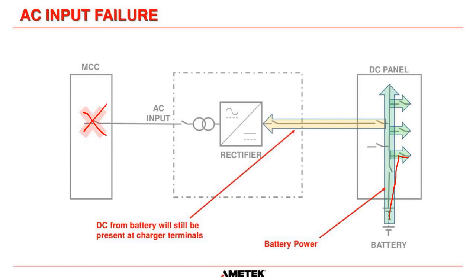But do be careful, because there is DC from the battery. If this disconnect is closed, you will still have backfeed from your DC panel back into your charger. So please be aware of that. If you have a power outage and you're going to go in and check your rectifier, there's still a backfeed there.